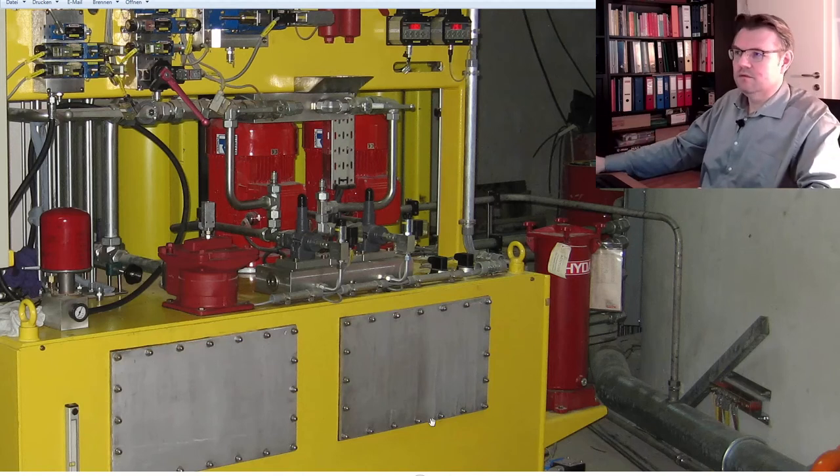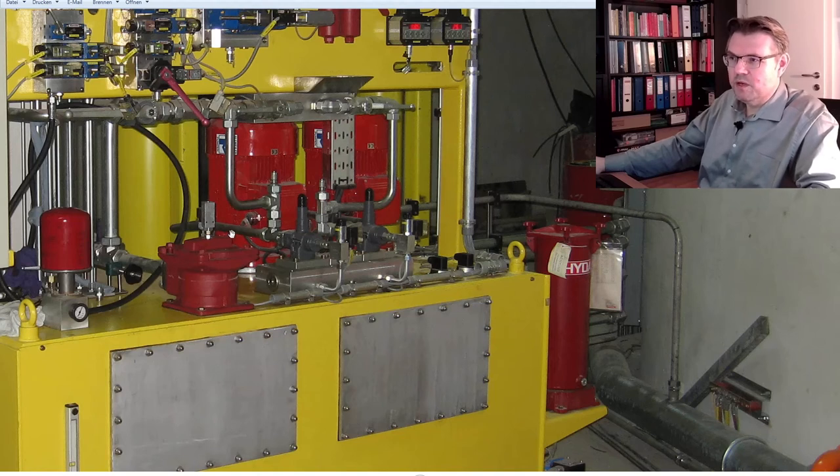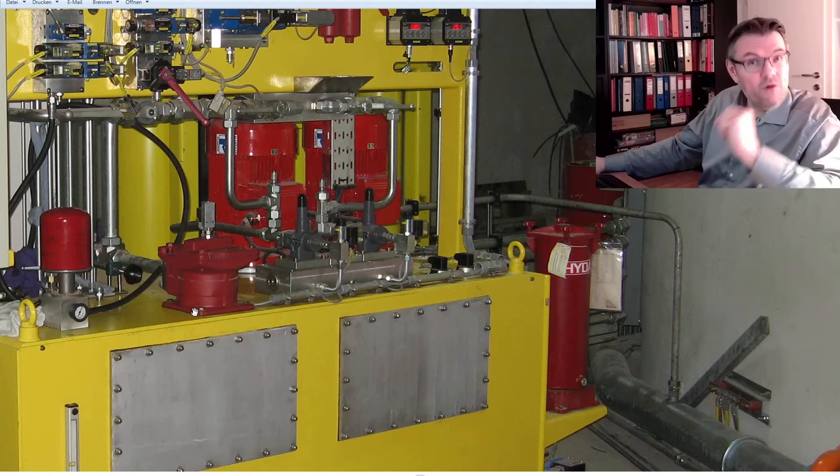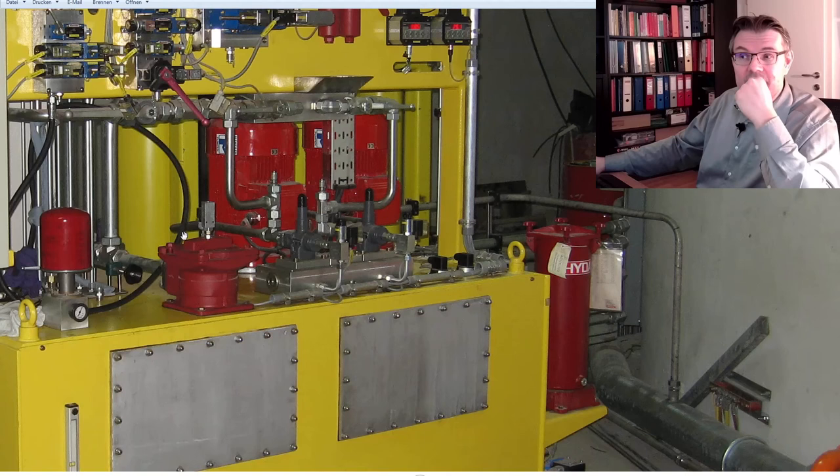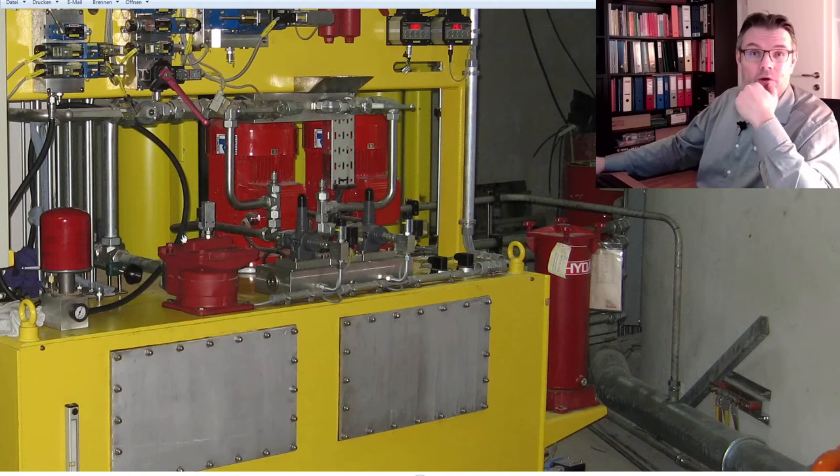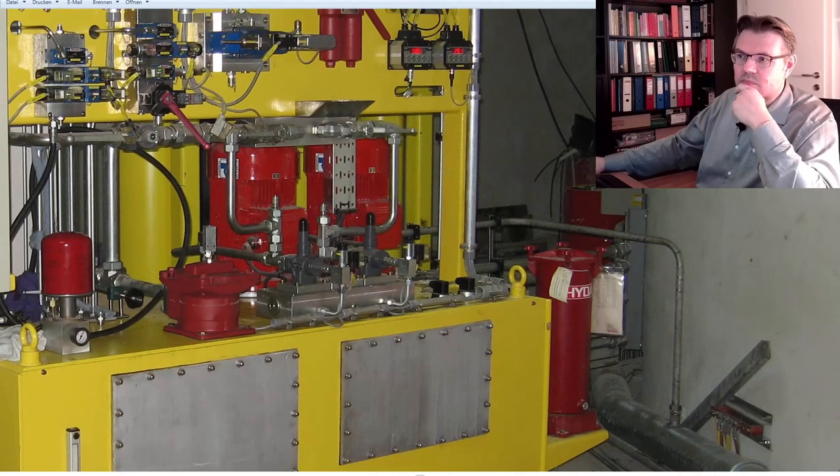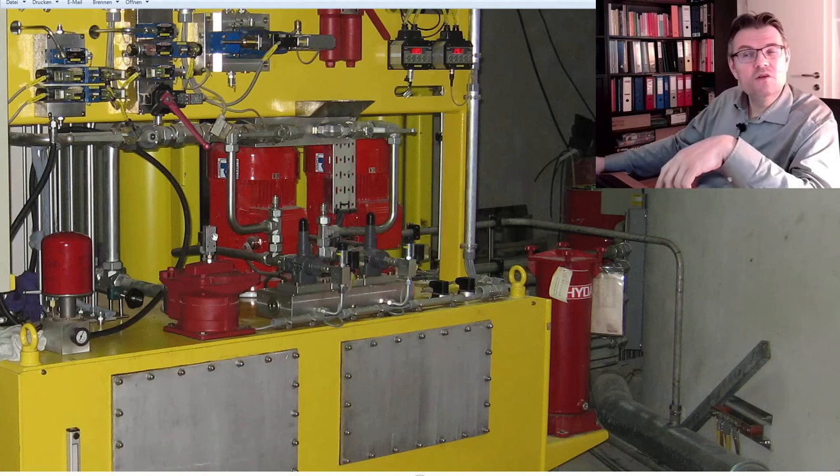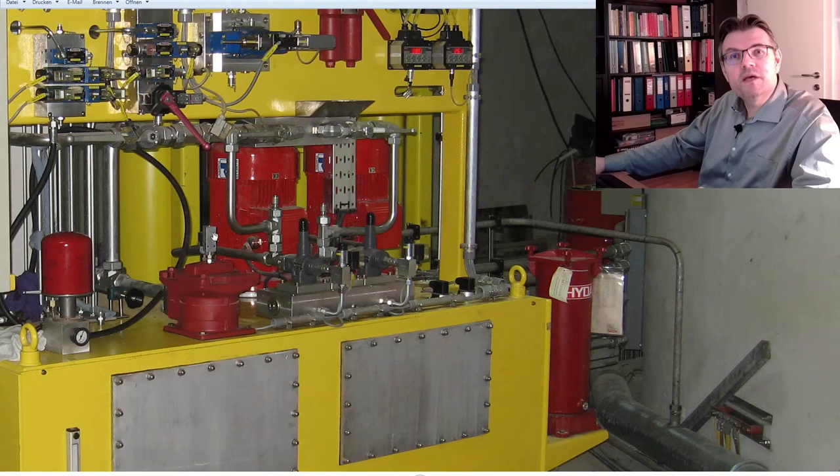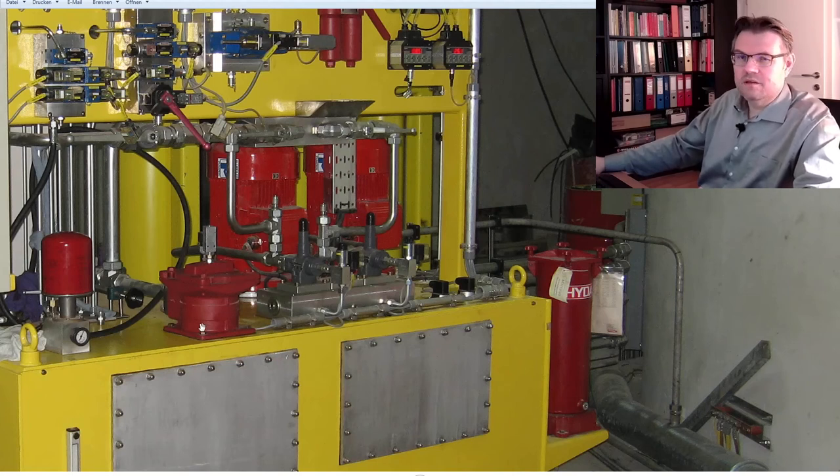It's this filter, this element. This here, this big one here, red part. This is the return line returning to the tank. This is a return line filter. Okay. So here we are using offline filter and an inline return line filter in this case. This thing here above, this is a pressure switch. So if the differential pressure is getting high, this will make a signal. Okay? This is the return line filter.